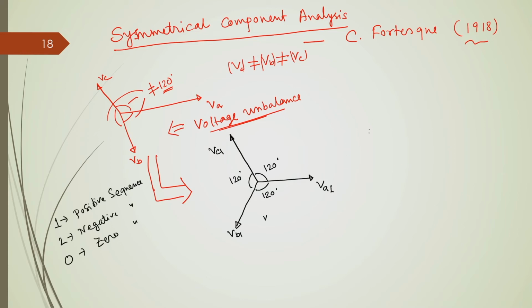In the positive sequence, the phase sequence of the supply voltage is the same as that of the original phasor. Here our phase sequence was A, B, C, because we assume that they are rotating anticlockwise. So, after A phase, B will come and then C will come. So, the phase sequence is A B C, the same as the original voltage. Now, in negative phase sequence, these voltage magnitudes are equal and they are exactly 120 degrees apart from each other, but their phase sequence is different. That means they are rotating in the opposite direction.